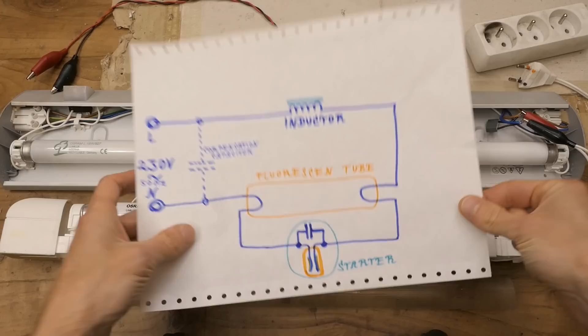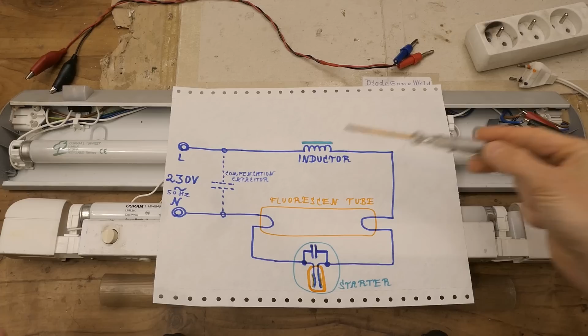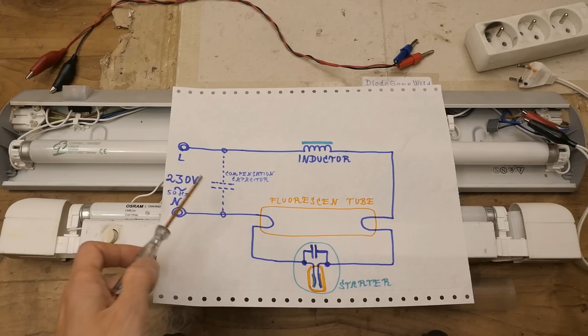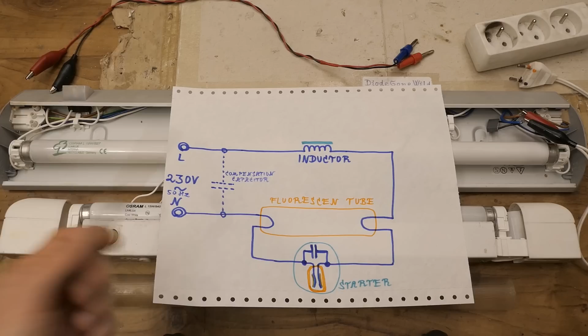Of course, I treated myself some dumpster fluorescent fixtures to be able to test it, and let's also explain the fixture and what the starter does in it. In a traditional fluorescent fixture with an iron inductor or magnetic ballast, the mains comes in. There can be an optional compensation capacitor to compensate for the power factor, which is otherwise on the inductive side. Sometimes it's just a small interference capacitor instead of a big compensation capacitor, and sometimes it's not installed at all.